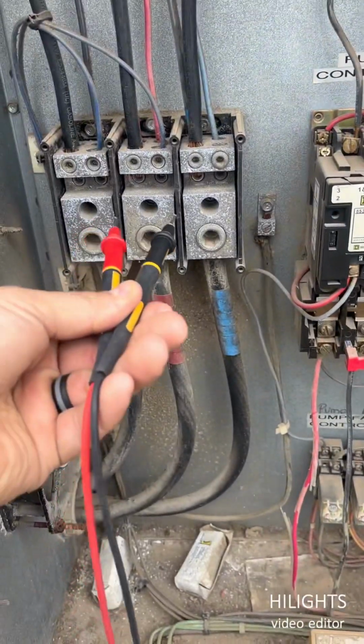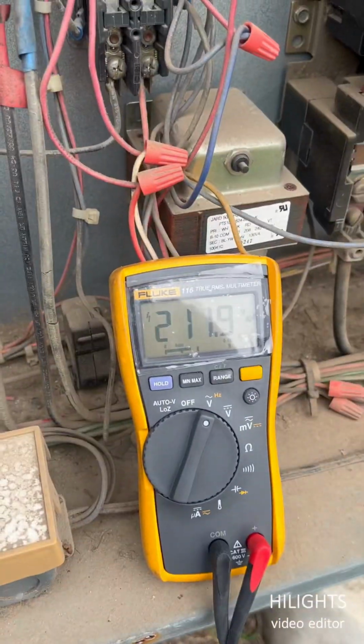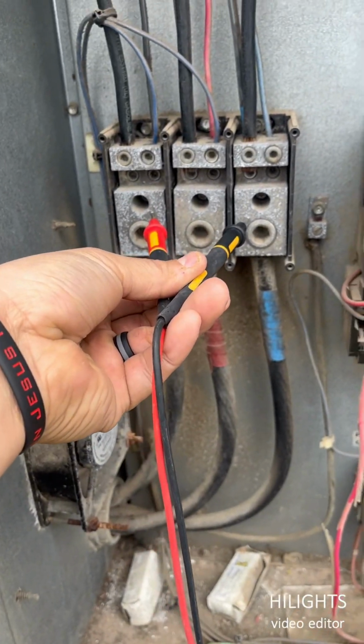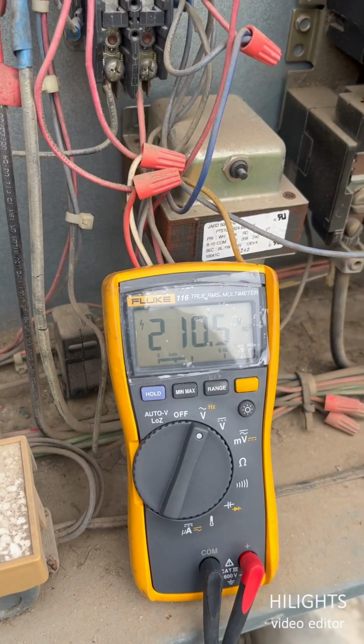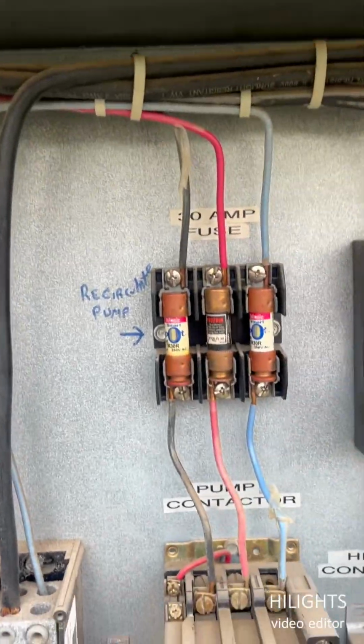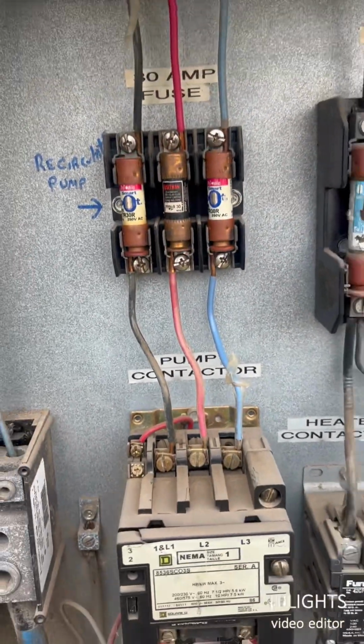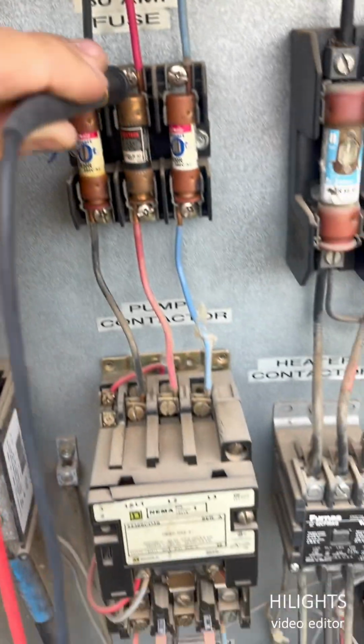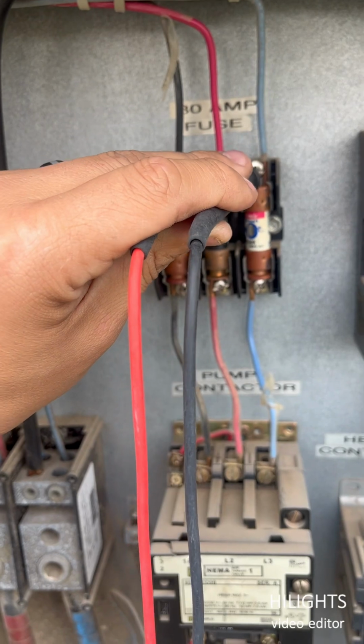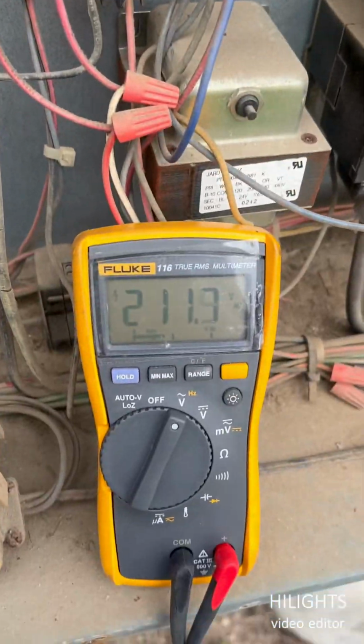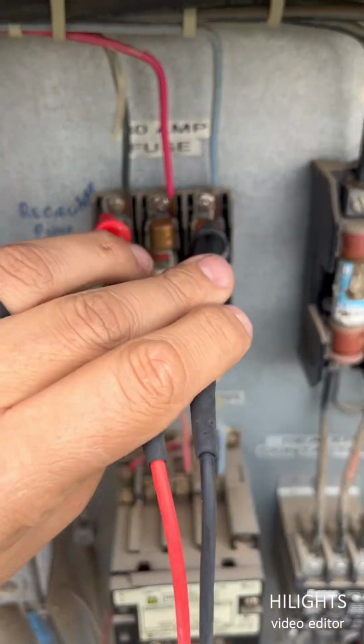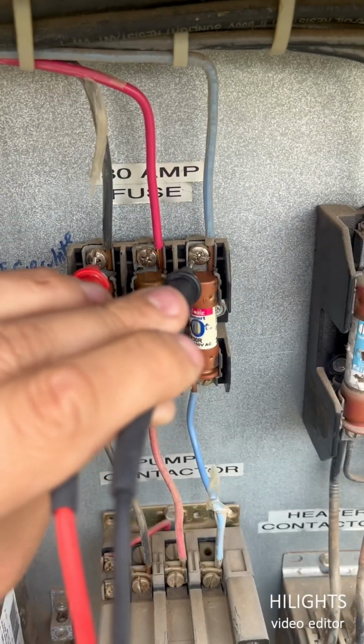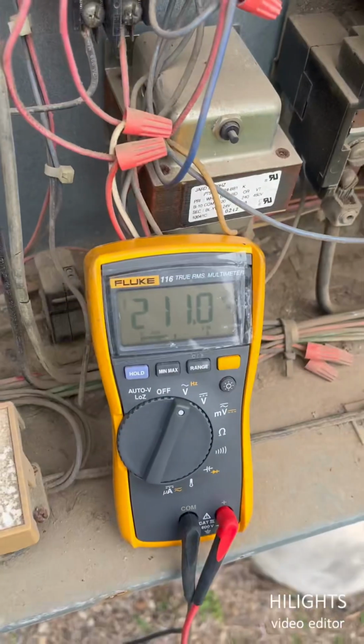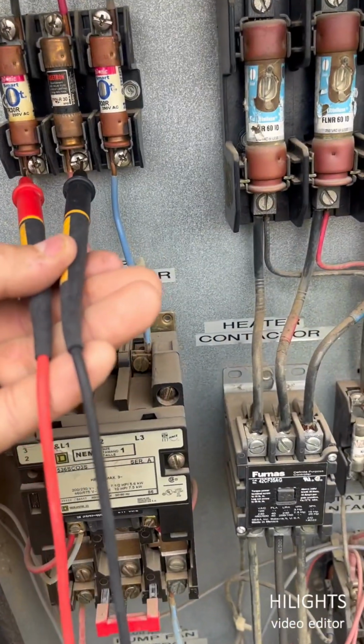First off, let's check for power, high voltage. You got 210 between those legs, between these, 211, and then 210. So we're good on power. Let's trace back the wires going straight to the pump fuses. You get power to the fuses. Getting 211 through those legs. Let's check the last legs, and 210. So you're getting power to the fuses.